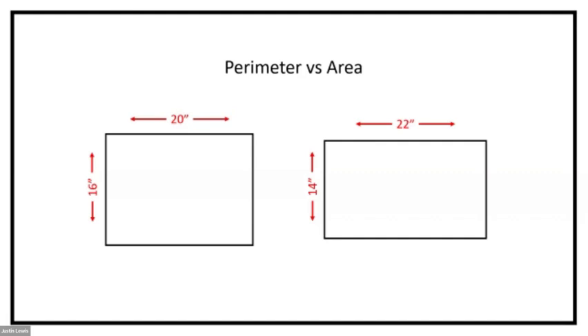So let's see what that does to the perimeter. So we see we have 72-inch perimeter on the original ductwork, and the redesigned ductwork also has 72. Well, no harm, no foul, no change. But let's see if that translates to area. We have 320 square inches of free area in the design duct, but only 308 square inches in the adjusted duct. Now, this will increase the pressure requirement of the system to move the same amount of air.